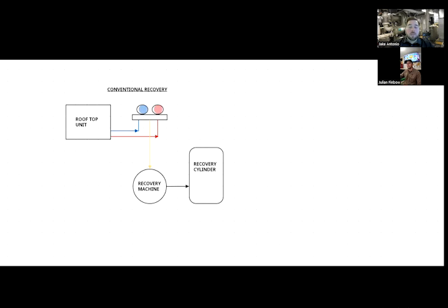Basically, it's a little bit different than the push pull because there's not a full circle of the refrigerant going between all of the equipment. What's happening is you have your gauges hooked up to your system and you're pulling it through your manifold, and then it's going through the charging hose into your recovery machine. The recovery machine is doing the work, doing the pumping and pushing that refrigerant into the recovery cylinder.